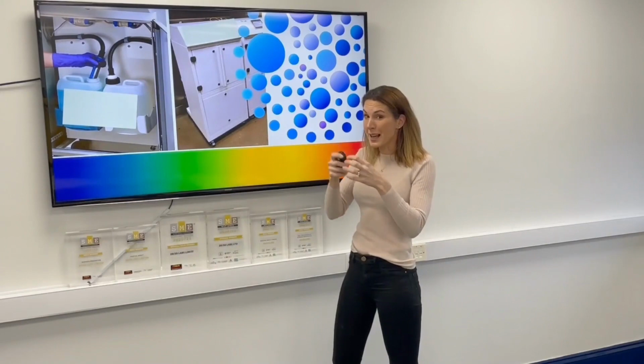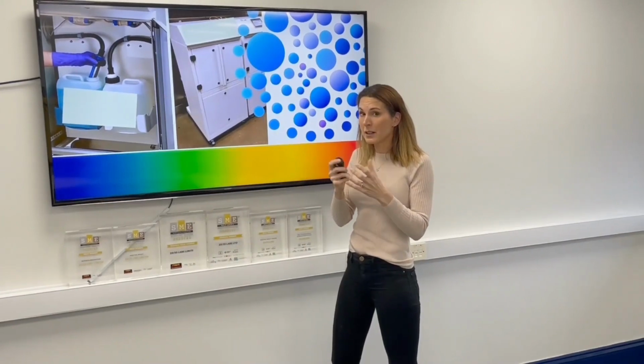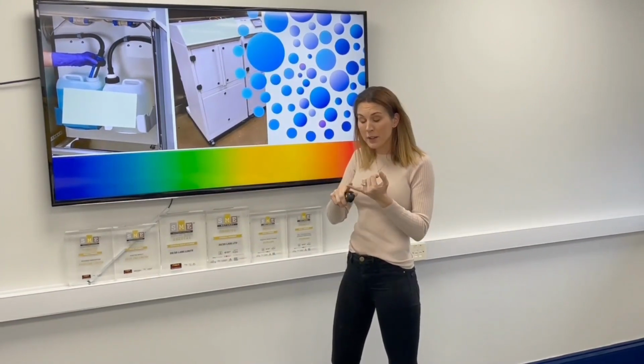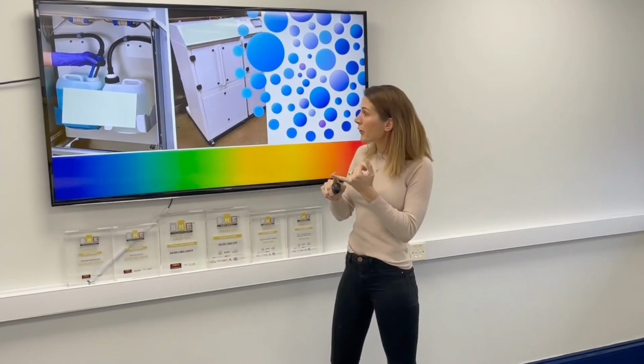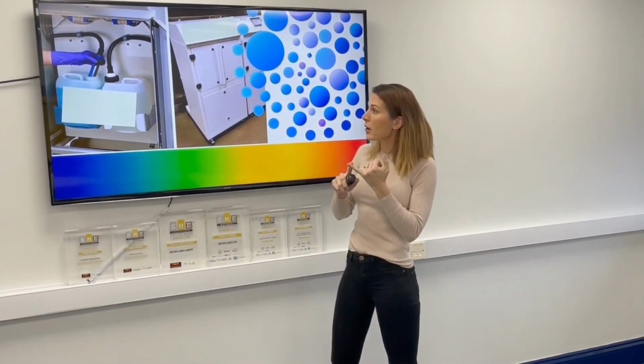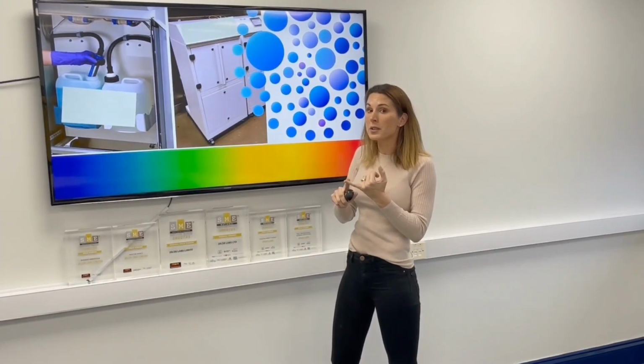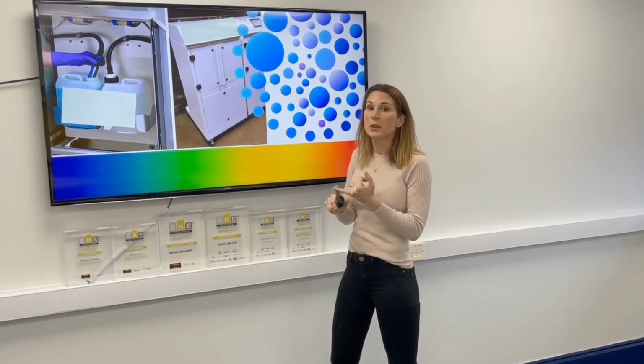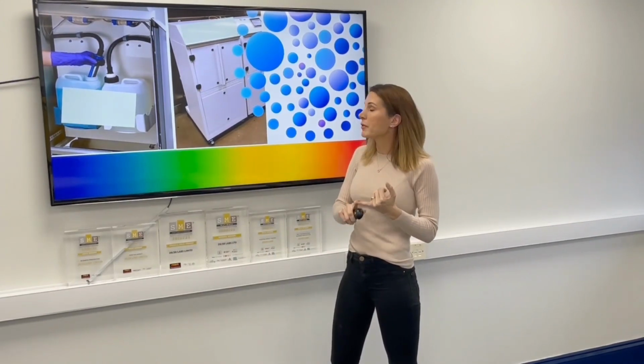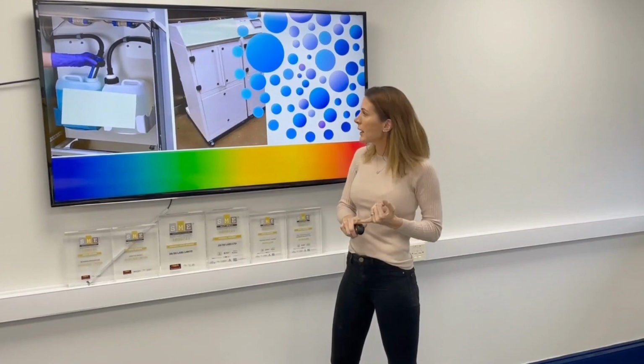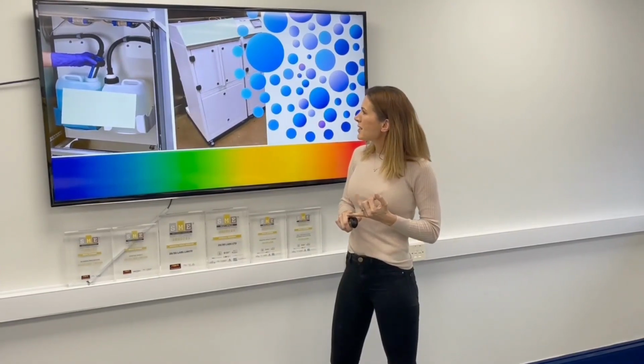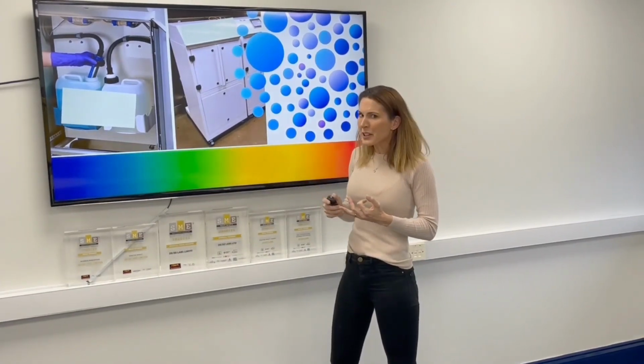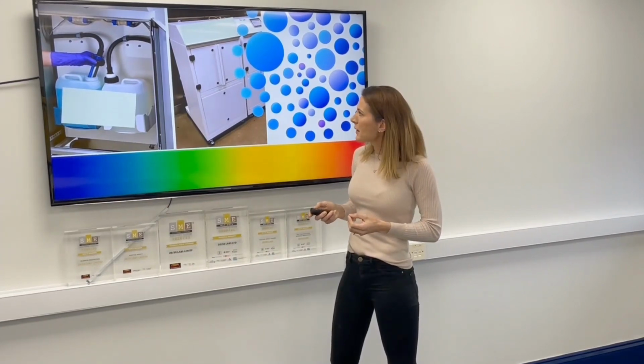Mixing oxidizers and acids is bad. There are two things that we know. One, the parts per million of the medical device, the peracetic acid, will not be correct anymore. That has an implication on the reprocessing efficacy of that device. Secondly, this stuff can create gas. You don't mix acids and oxidizers.